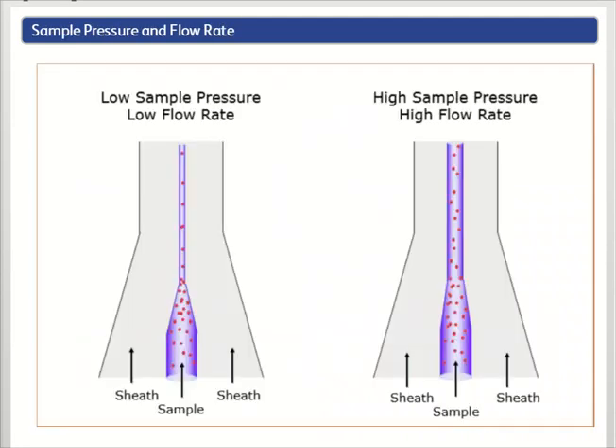The sample pressure must always be greater than the sheath pressure. The sample pressure can be adjusted to increase or decrease the width of the sample core, which can increase or decrease the sample flow rate, or events per second. A wider sample core can increase the event rate because it allows more cells to enter the stream within a given moment.